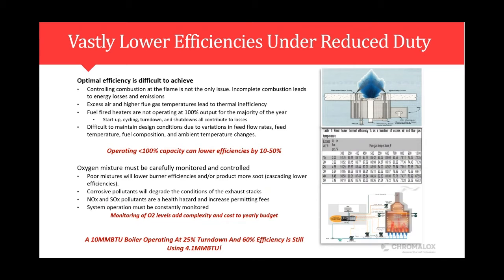So again, getting back to the case where we're not operating 100% all day, we have startups and shutdowns and turn downs. We know that the true efficiency of these systems over any given day is much less than what the advertised efficiencies are. And I talk about the oxygen metering again with that excess air. You have to add that air to make sure that you have good efficiency of combustion, and you're not sending fuel right out the flue stack, because that becomes problematic from other aspects. So again, the increased air percentage just reduces those efficiencies.